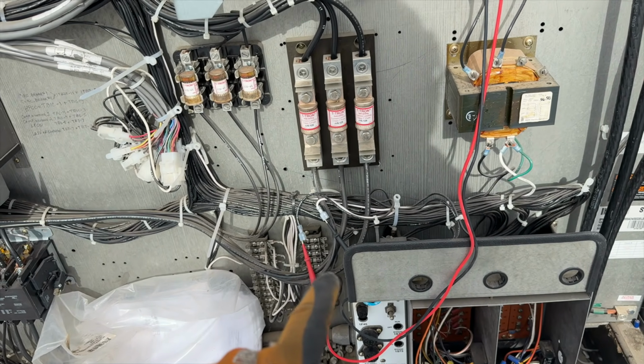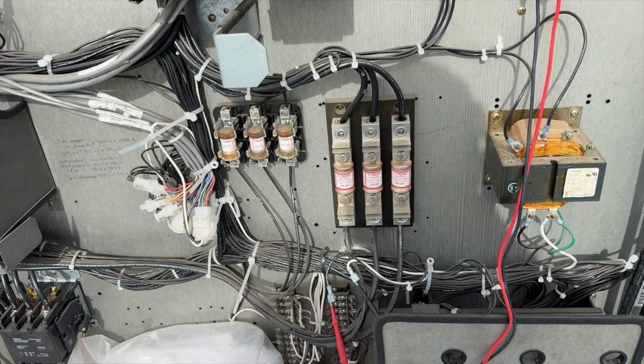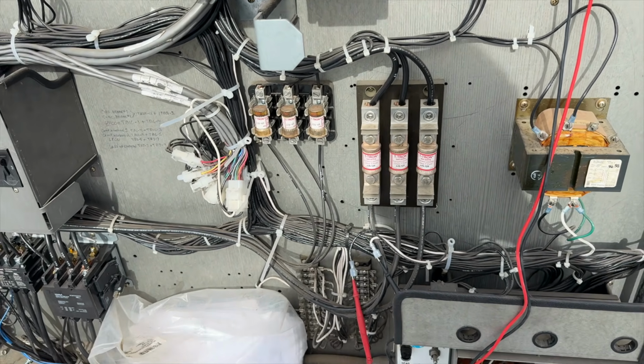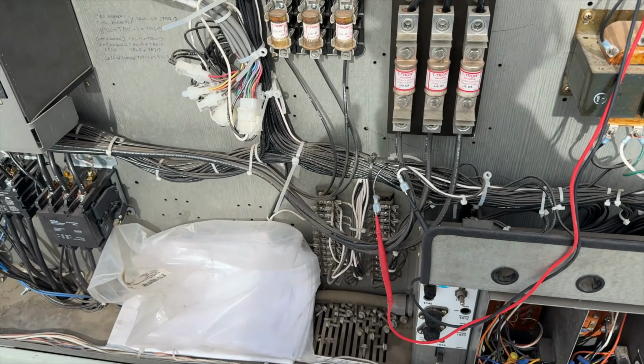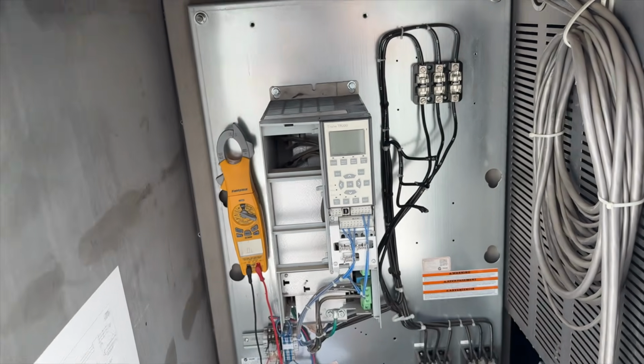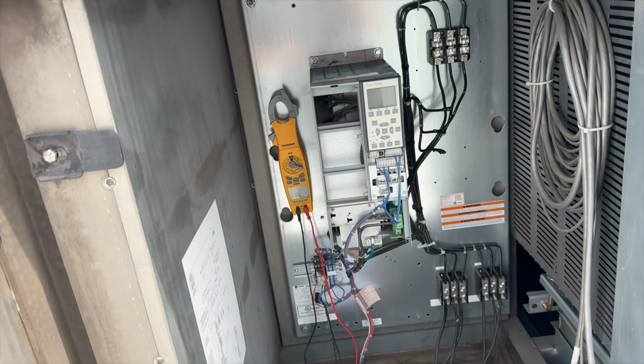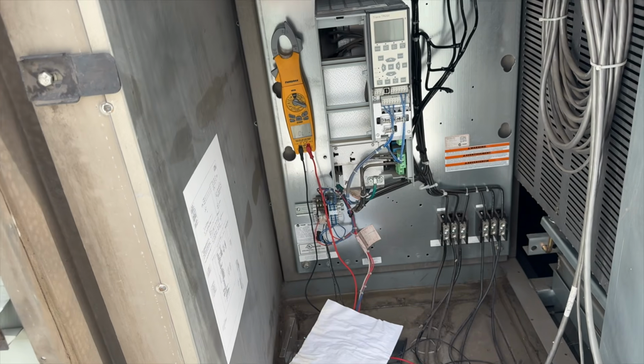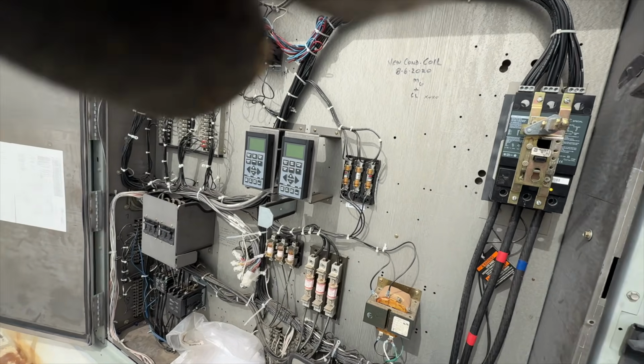Now we need to figure out about bypassing the motor itself, or bypassing the VFD, so we can get that motor running. All right, so we got it all wired in, so we're gonna go ahead and see if we can get this motor to operate and then go from there. Alrighty, here we go, moment of truth.